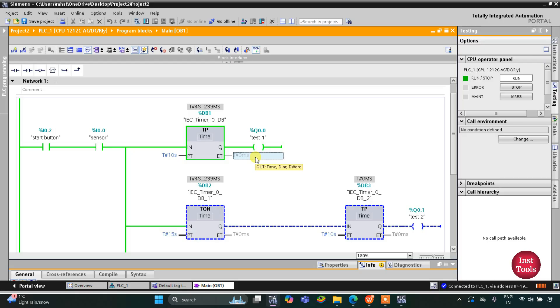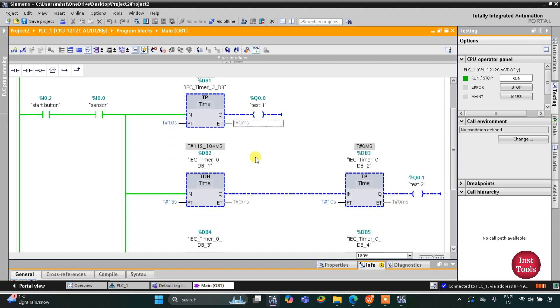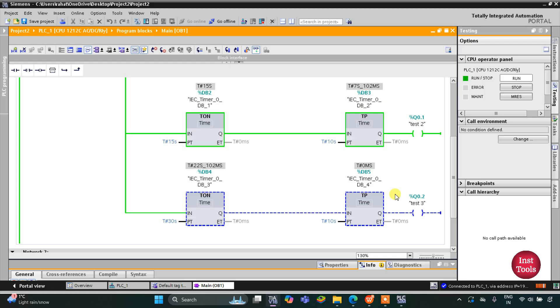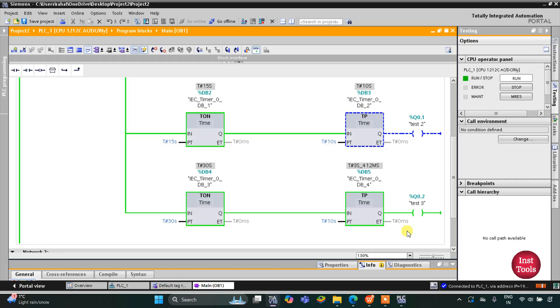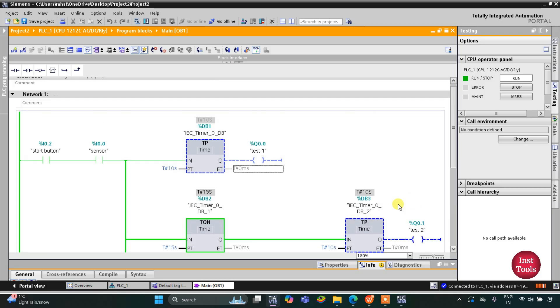When I turn on the start button nothing happens, but when the sensor gets activated, the machinery for Test 1 activates and runs for 10 seconds. After that Test 1 stops, then there is a 5-second delay, and Test 2 begins — the machinery for Test 2 operates for 10 seconds. After Test 2 stops, it waits another 5 seconds and then Test 3 starts. After 10 seconds, the machinery for Test 3 also stops. That was all about this example — thank you for watching.